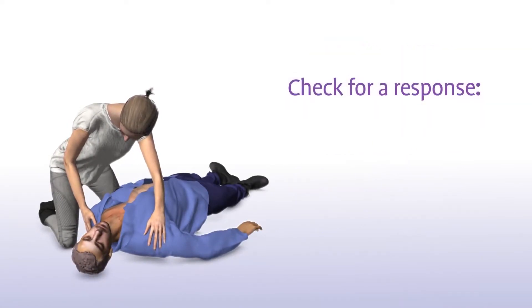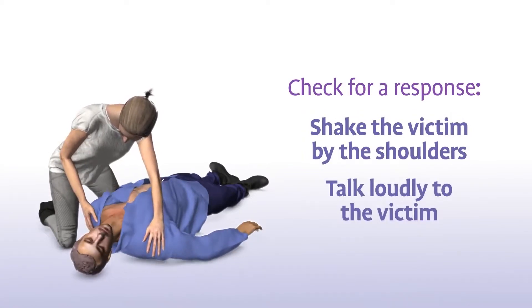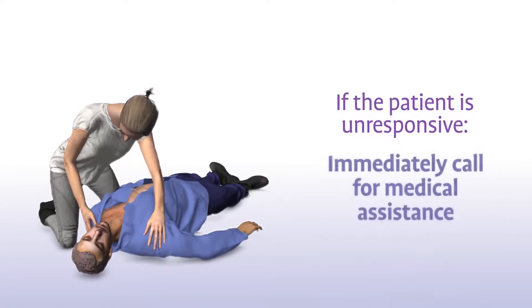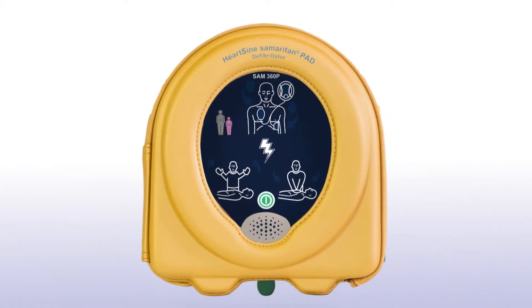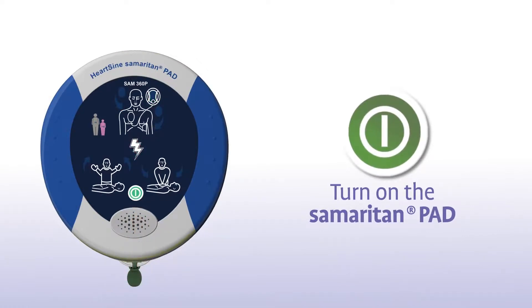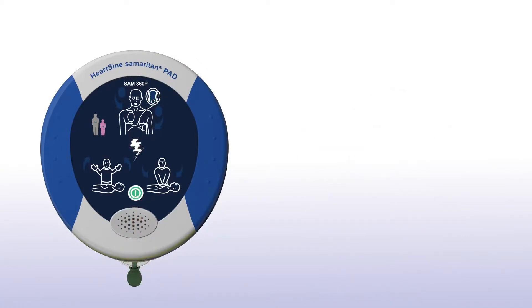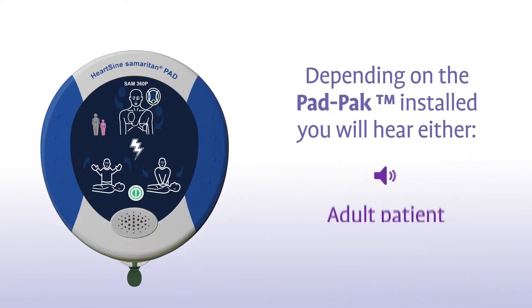Check for a response by shaking the victim by the shoulders and talking loudly to the victim. If the patient is unresponsive, immediately call for medical assistance and get the Samaritan PAD as quickly as possible. Press the green on-off button to turn on the Samaritan PAD. Depending on the Pad-Pak currently installed, you will hear either an adult patient or a child patient prompt.